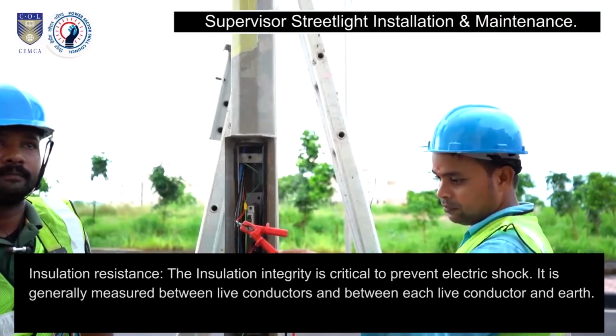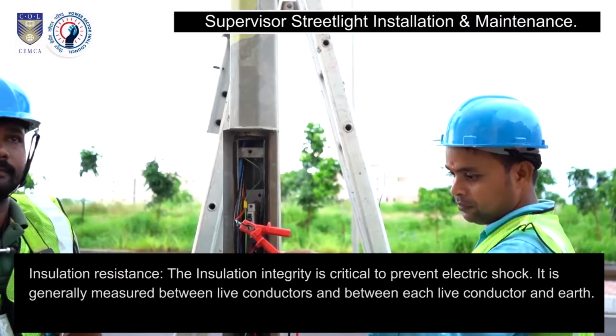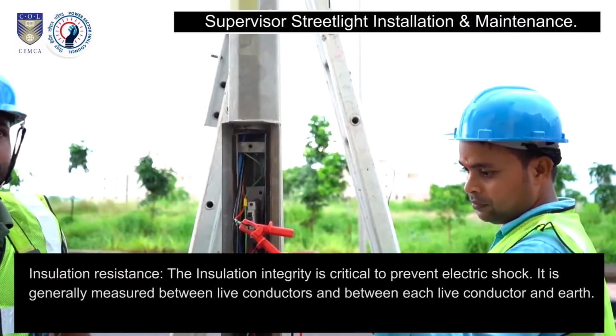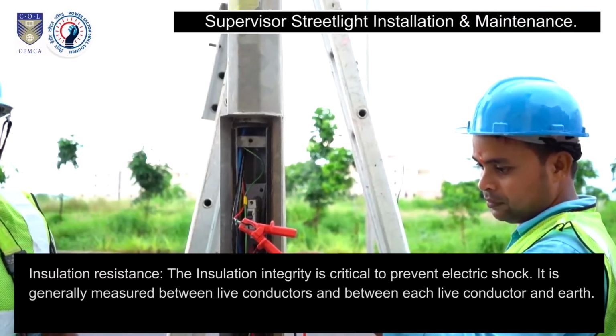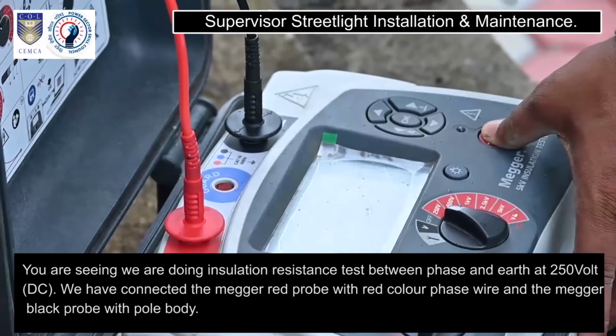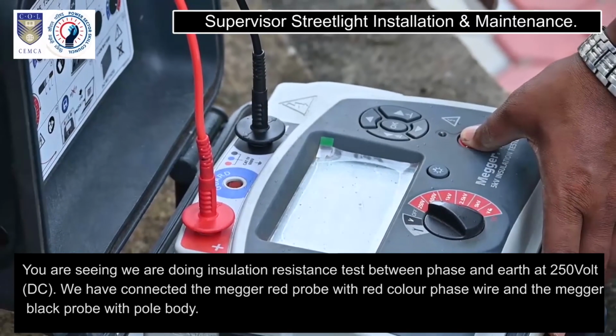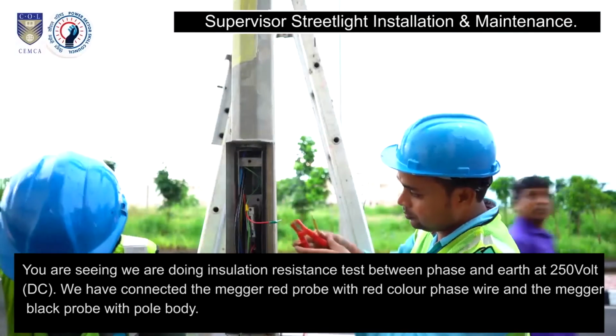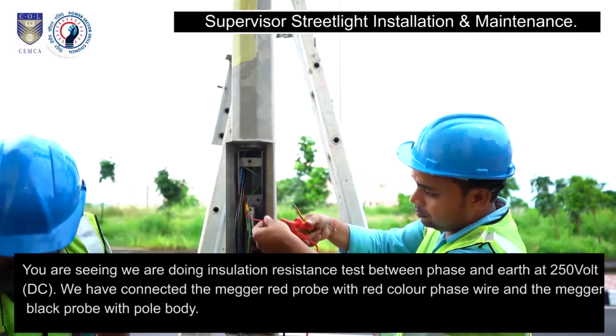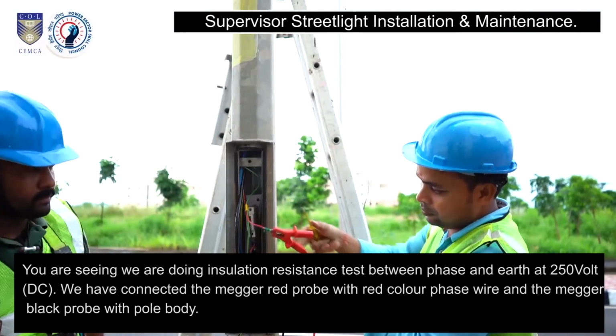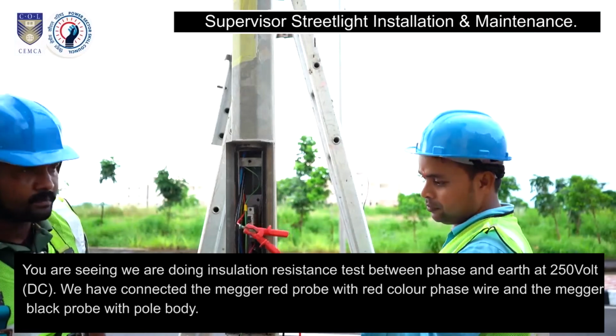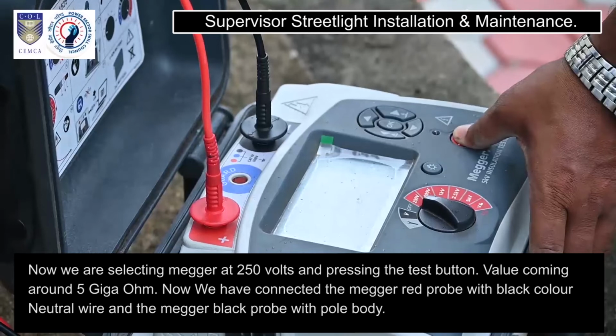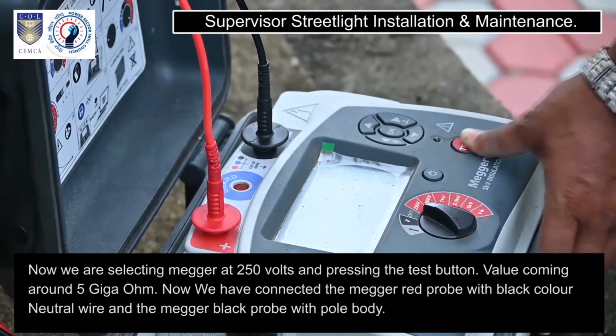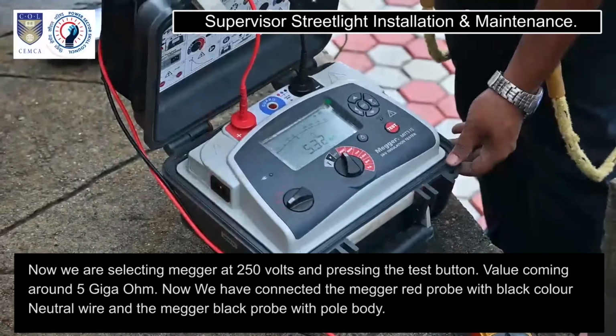Insulation resistance. The insulation integrity is critical to prevent electric shock. It is generally measured between live conductors and between each live conductor and earth. You're seeing we are doing insulation resistance test between phase and earth at 250 volt DC. We have connected the megger red probe with red color phase wire and the megger black probe with pole body. Now we are selecting megger at 250 volts and pressing the test button. Value coming around 5 gigaohm.